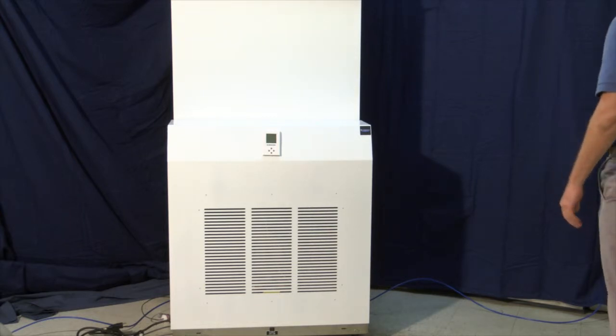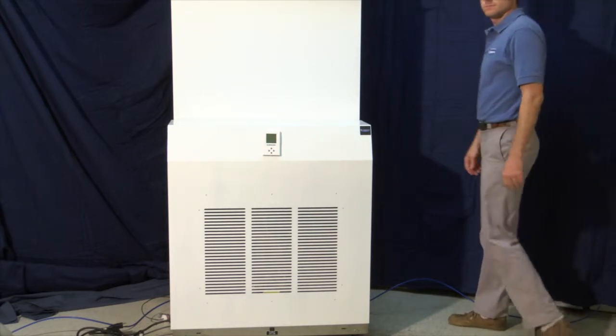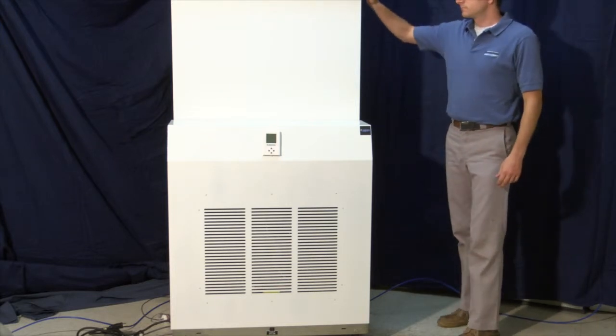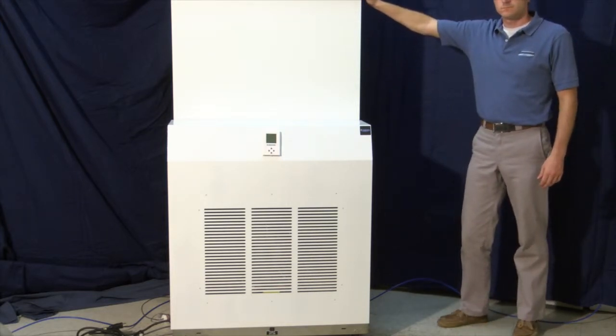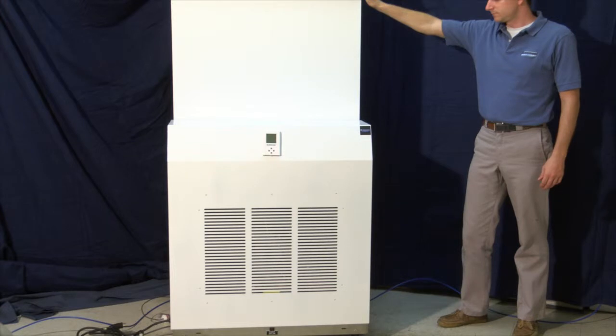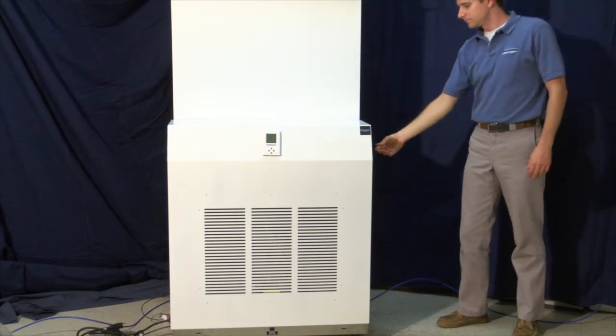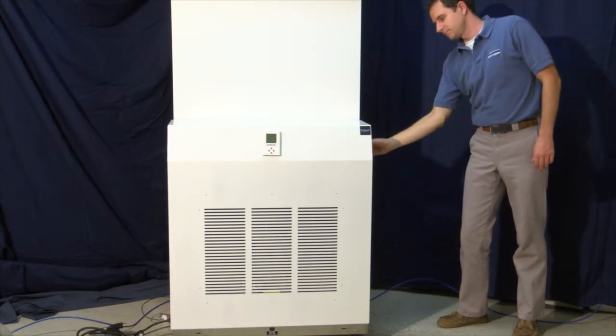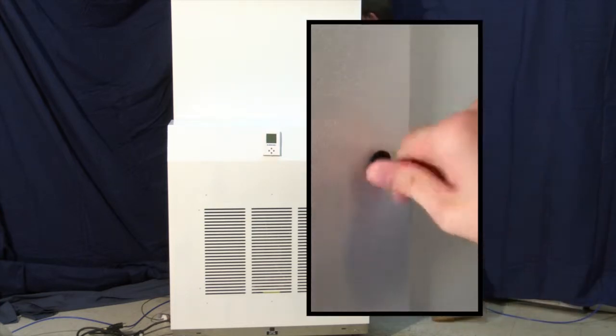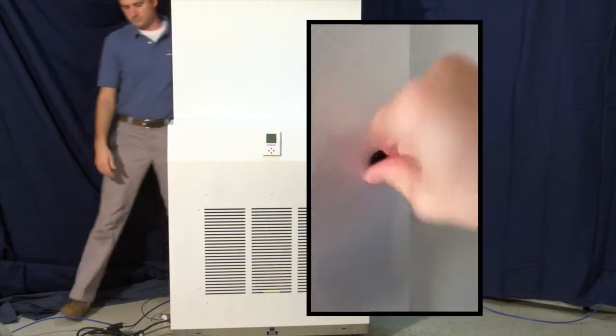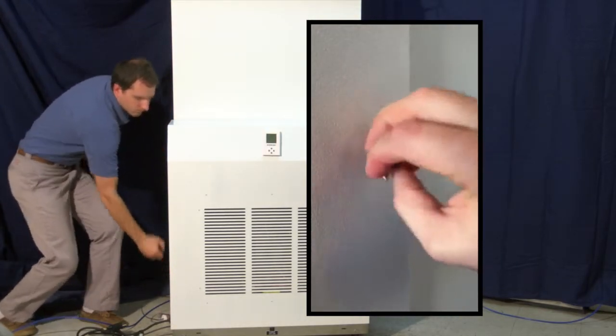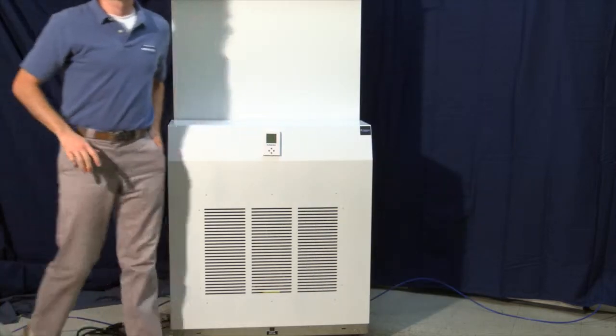When starting up a new system, or restarting a system that has been shut down during the warmer season, you will need to access the Mist-Free's water pan to check for debris from construction or installation and prime the transducers with water. To do this, remove the 3 thumb screws on each side. After removing all 6 screws, you may remove the unit's fan cover.